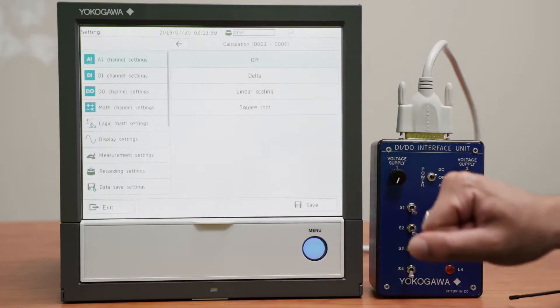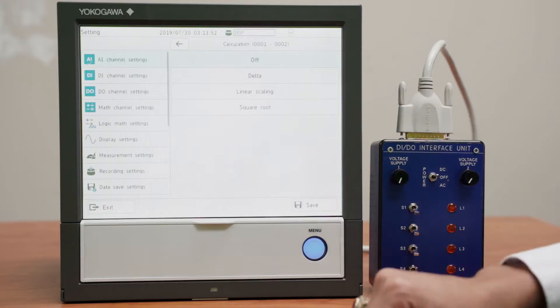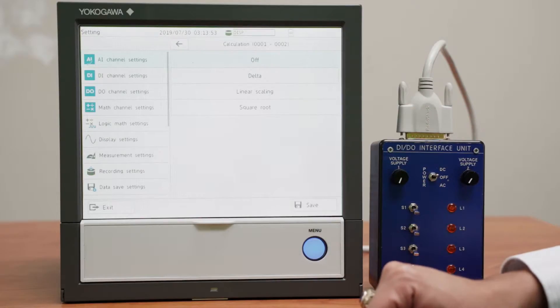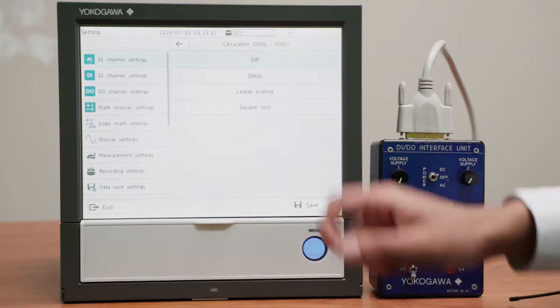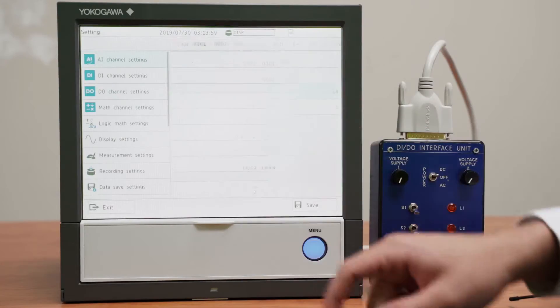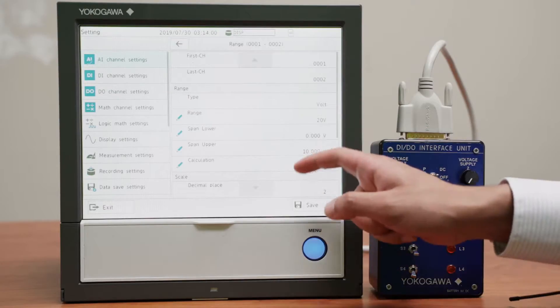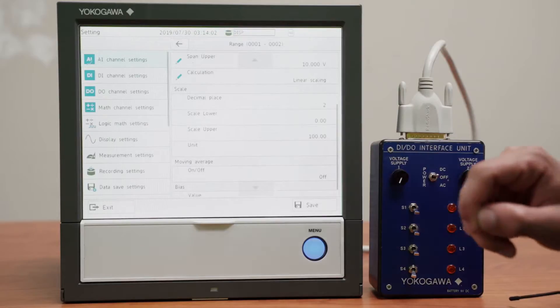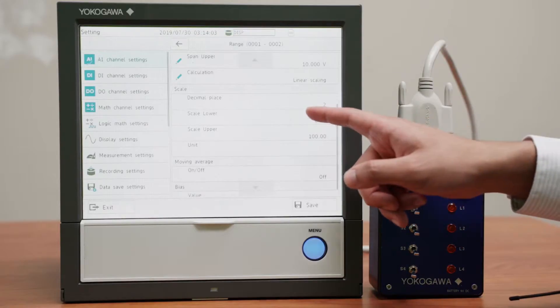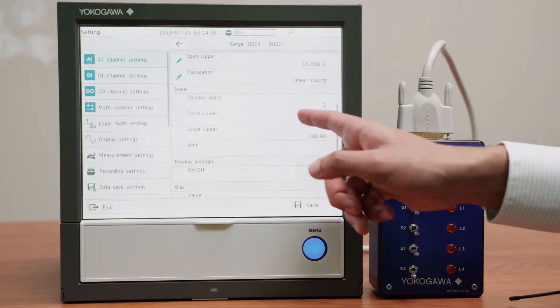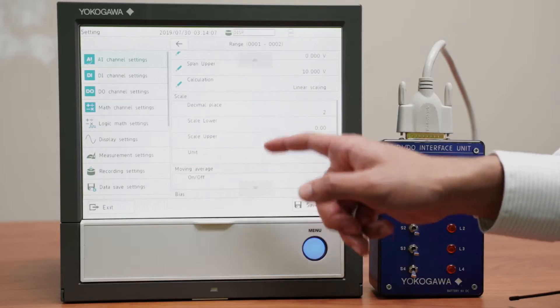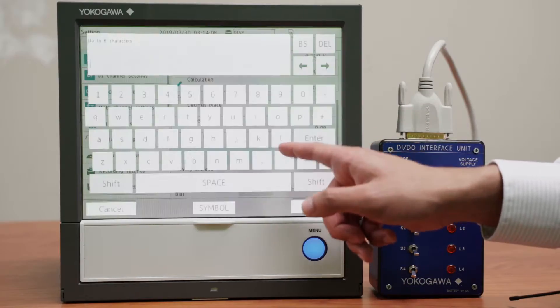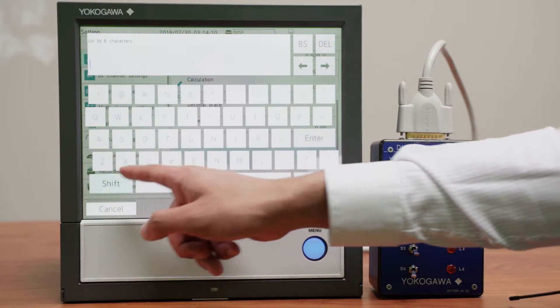And since this voltage is measuring an amount of gallons per minute, I will need linear scaling. And in the scale I'll leave that to 0 to 100 and make the units gallons per minute.